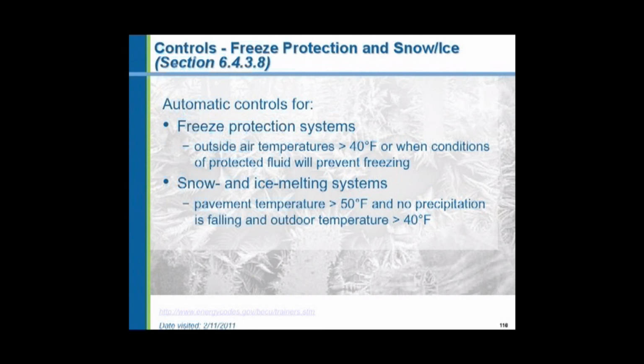Freeze protection, snow melt systems. They say basically when it's not needed, shut it off. If it's warm outside, shut it off. If it's below freezing outside, it's a snow melt system and it's not snowing, shut it off. If you have heat tape protecting something and it's below freezing, obviously you want it to continue running. But above freezing, shut it off.